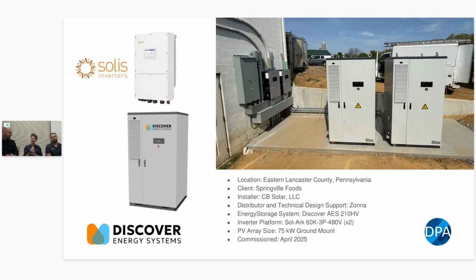Good to know. In America we go through the same UL listings, 9540. The prerequisite to 9540 is the UL 9540A test, which tests propagation for thermal runaway between cells, and whether it spreads outside to other cabinets. We've passed that in such a way that you don't need to leave space between the two - they don't even get propagation through the module.